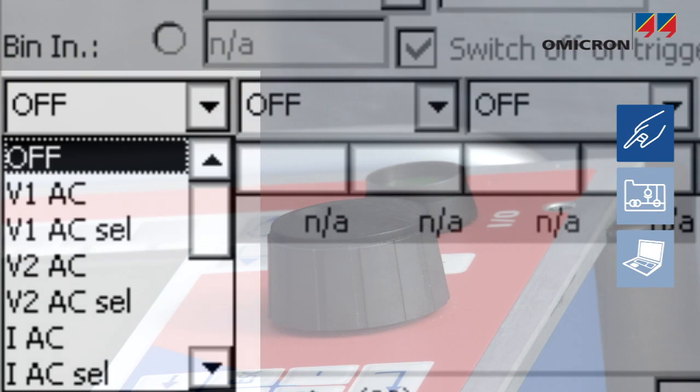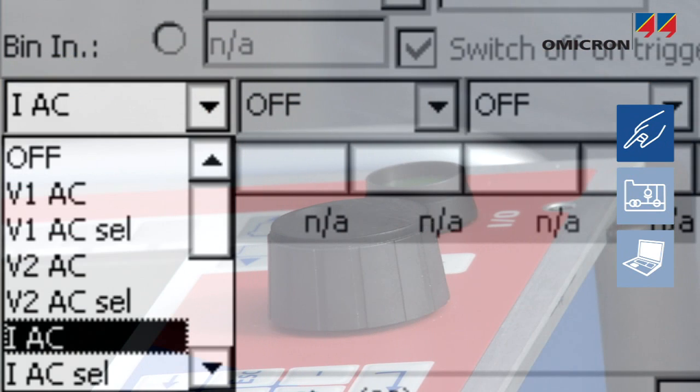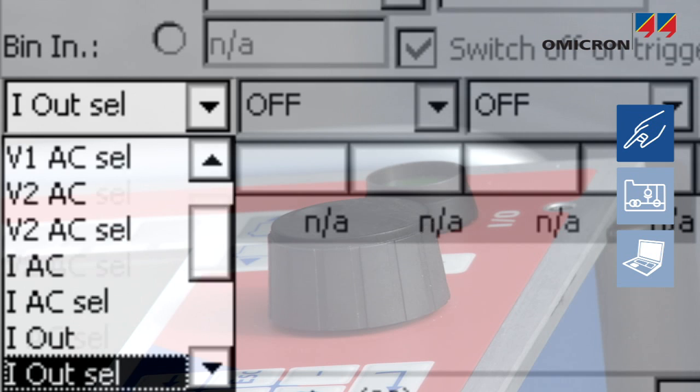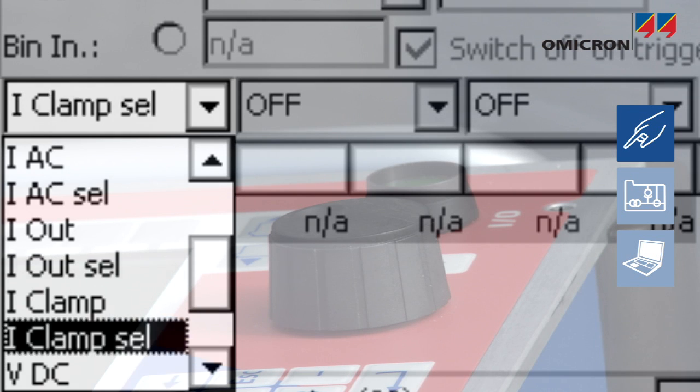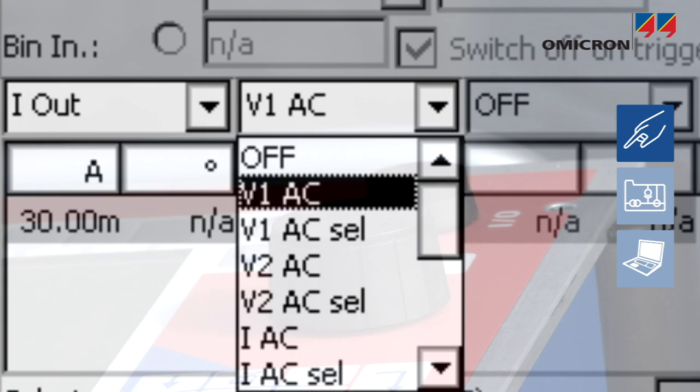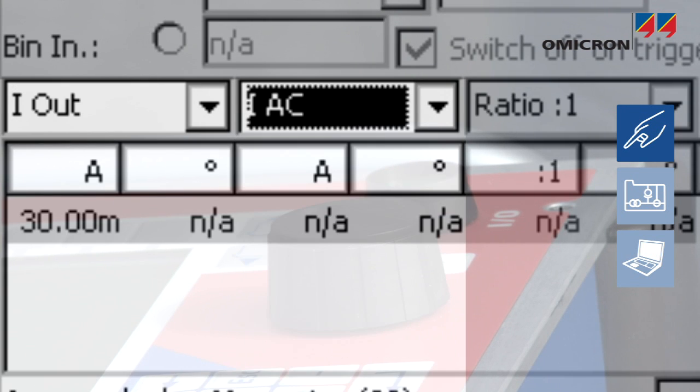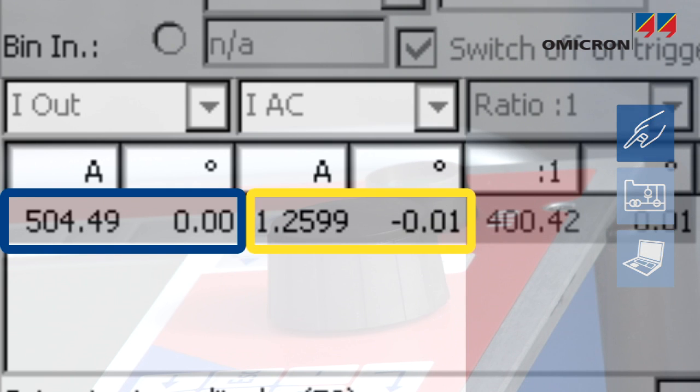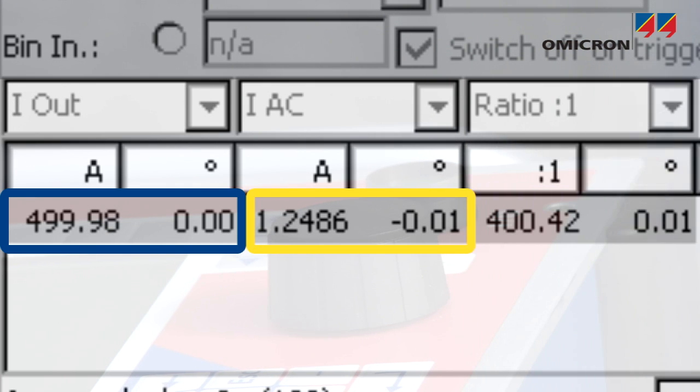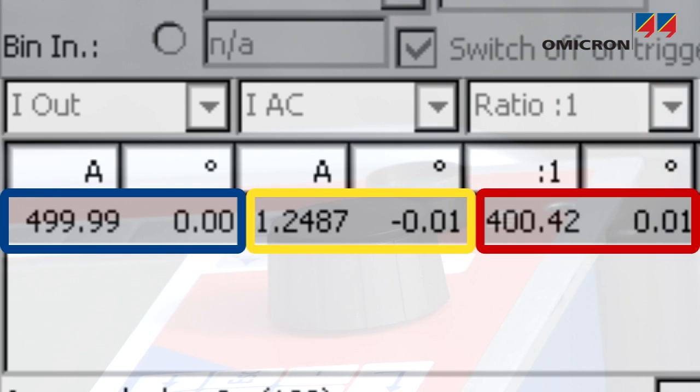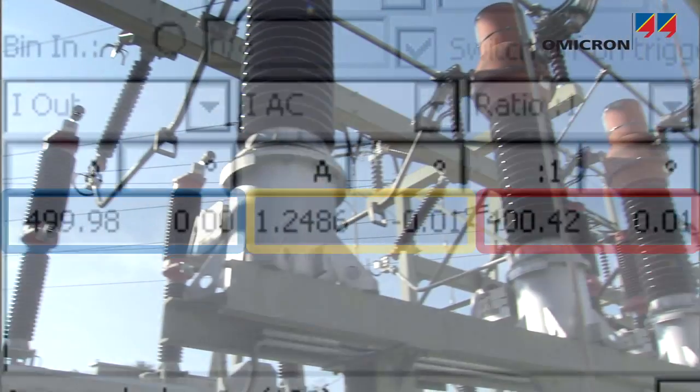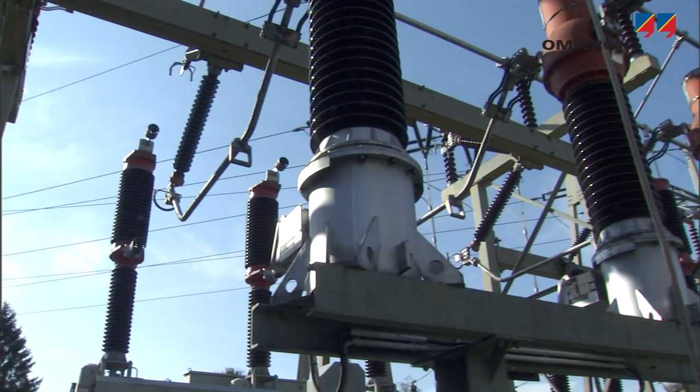Measurements can be performed easily. Two quantities can be determined at the same time, such as the primary and secondary currents of a CT, which are measured in amplitude and phase. From these two values, the CPC can calculate a third one, such as the ratio and polarity of a CT.